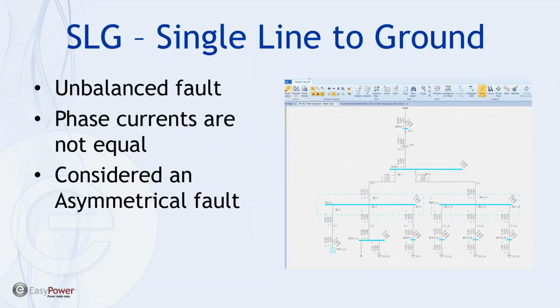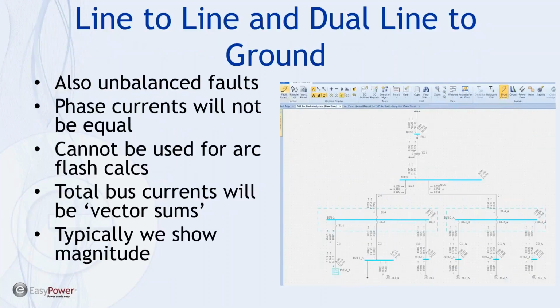Now, unbalanced faults, characteristic would be a single line to ground, in which the phase currents are not equal, and again it's considered an asymmetric fault. EasyPower will show these results, but again it won't be used in calculating arc flash. Another asymmetric fault, or two others, would be line-to-line faults and then dual line to ground. And as we'll see, the phase currents are not equal.